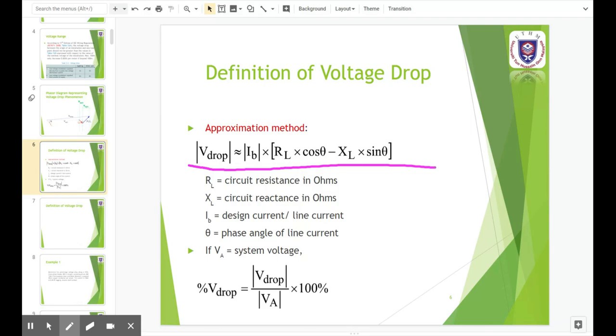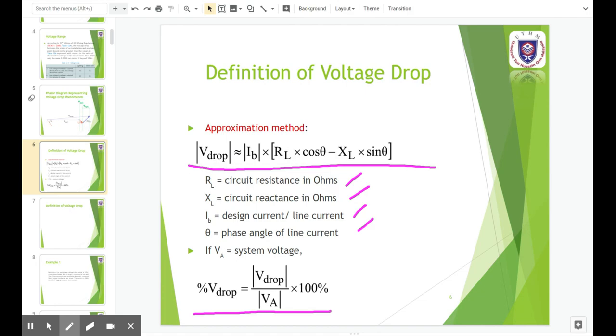Where rl is the circuit resistance in ohms, xl is the circuit reactance in ohms, ib is the design current or line current, and theta is the phase angle of the line current. We can also get the percentage of the voltage drop, where va is the system voltage or the phase voltage.